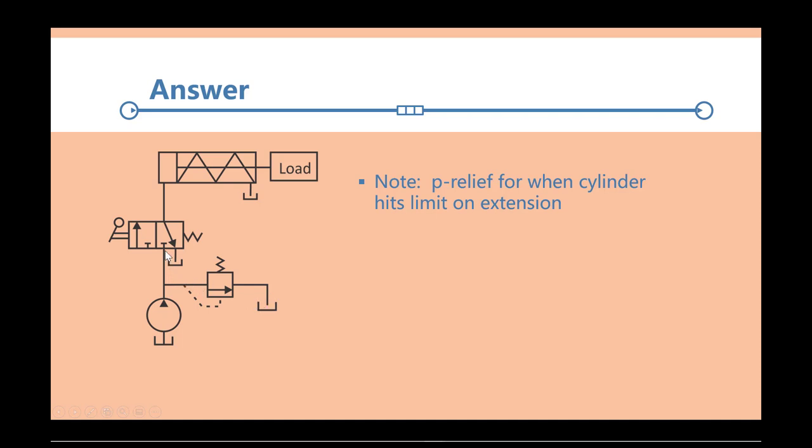If we actuate the valve, so we push on the lever, and that makes this envelope active, then our fluid flows through, goes into the cylinder, into the cap end of the cylinder, and pushes the cylinder to the right. Now this is a special cylinder in that it has a spring in it. And that's a bias that if you don't actuate it, then what the spring wants to do is it wants to retract the cylinder. So we have pressure to extend the cylinder, and then no pressure to retract the cylinder.